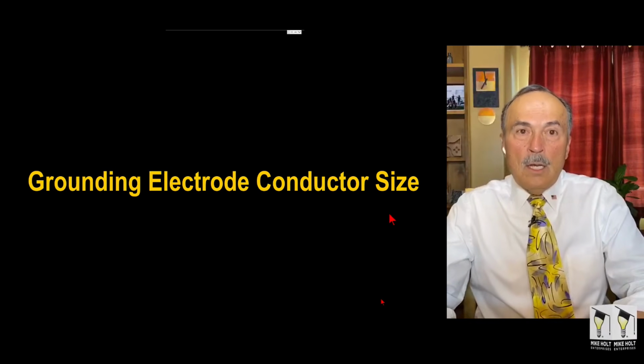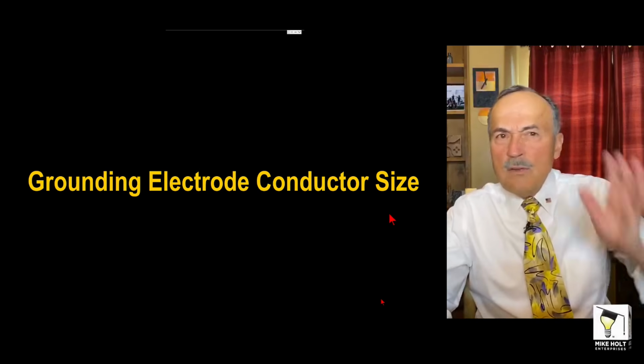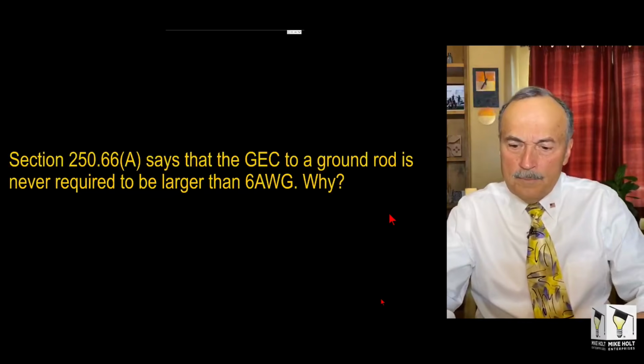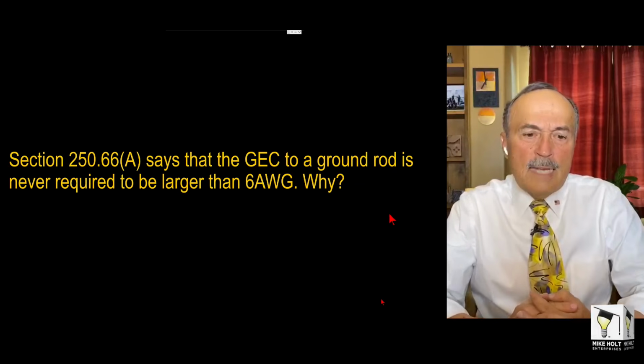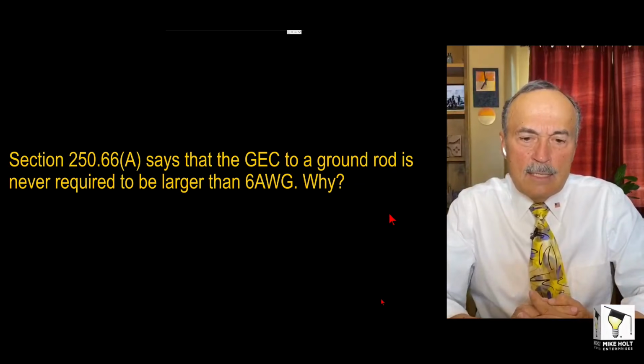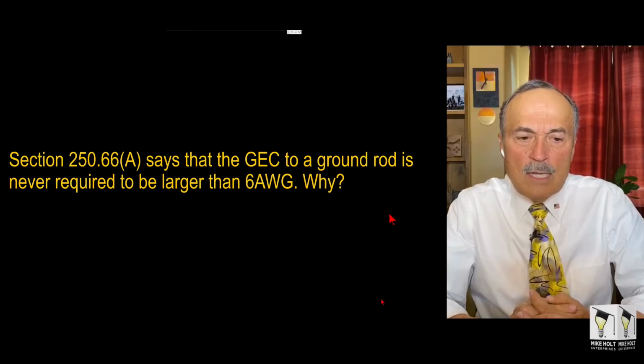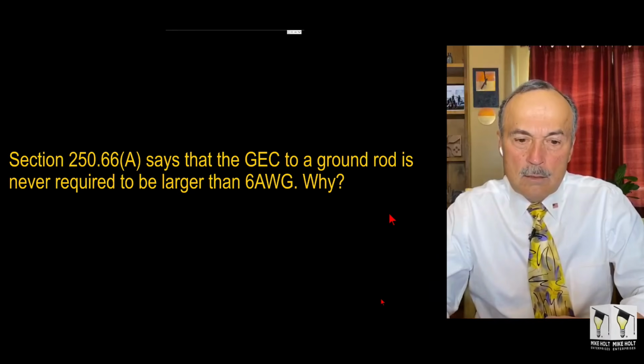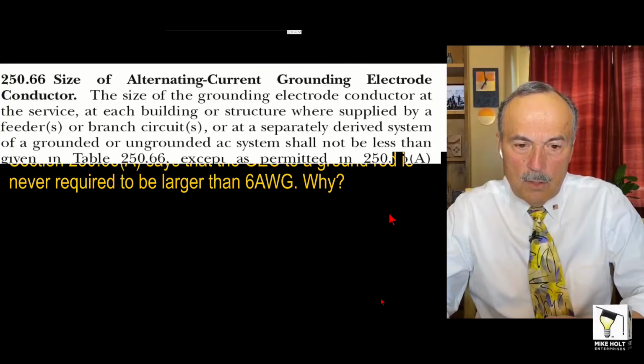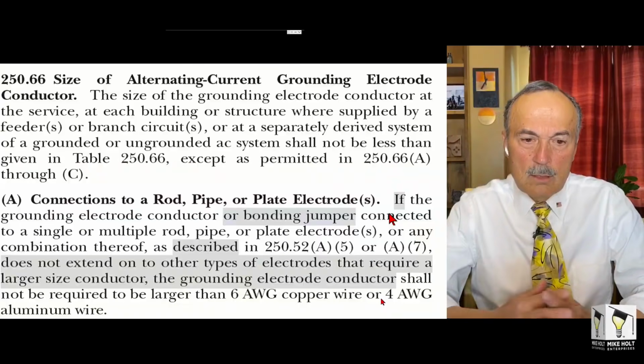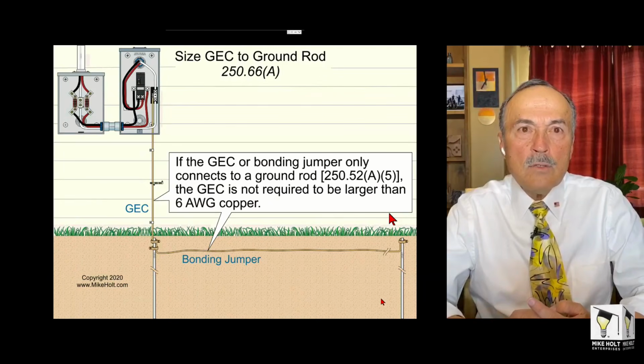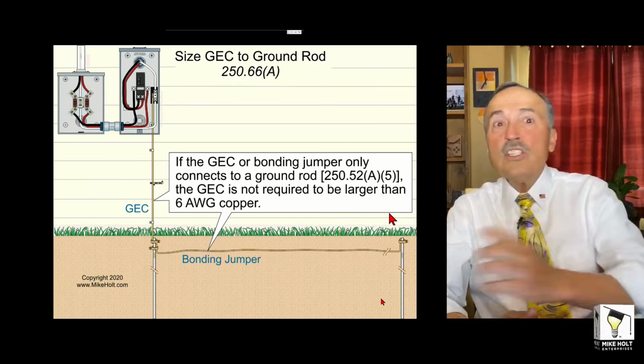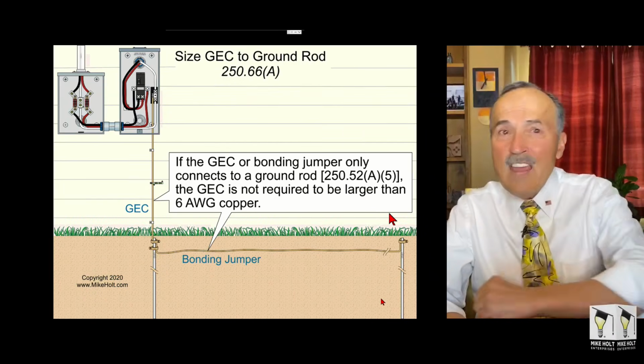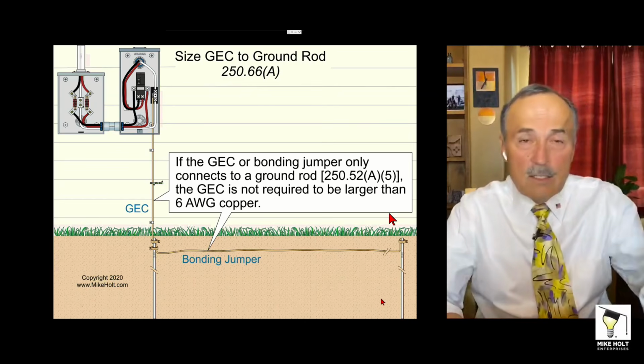Okay. Grounding electrode conductor size. We've already hit this once before. A quick one. Mike, section 250.66(A) says that the grounding electrode conductor to a ground rod is never required to be larger than 6 gauge. Why? Well, let me go over here. How many amps do you think is going to go to a ground rod? We just covered all kinds of systems. We talked about every single system about a ground fault, every single system.